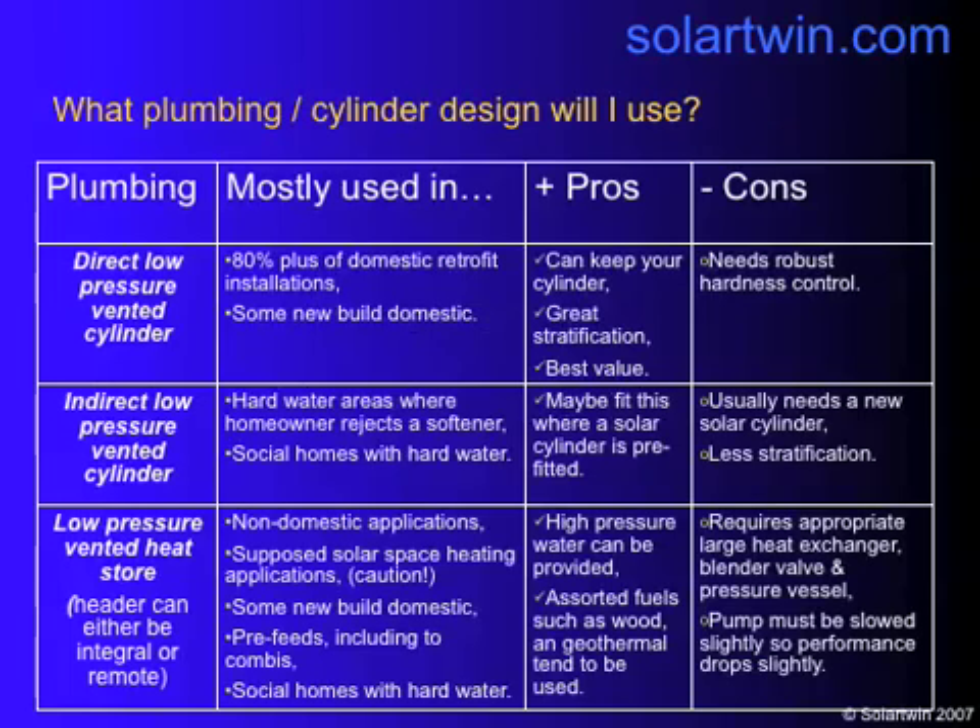We recommend that if you want high-pressure water, you use a low-pressure vented heat store — the header can be integral or remote. That works for all sorts of systems and will give you high-pressure water with all sorts of fuels: wood, geothermal, and so on. But you do need a large heat exchanger, a blender valve, and a pressure vessel. We may also need to slow the pump down, so performance drops slightly.